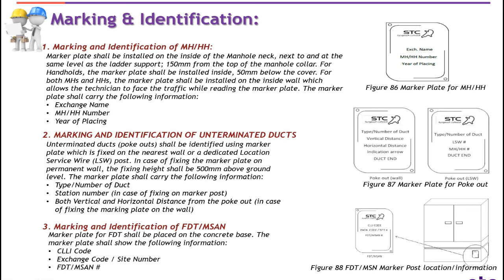The marker plate shall carry the following information: exchange name, manhole or handhole number, and year of placing. Number two: marking and identification of unterminated ducts — unterminated ducts or pokeouts shall be identified using a marking plate fixed on the nearest wall or a dedicated location service wire or LSW post. In case of fixing the marker plate on a permanent wall, the fixing height shall be 500 mm above ground level. The marker plate shall carry: type and number of ducts, station number. In case of fixing on a marking post, both vertical and horizontal distance from the pokeout shall be shown.